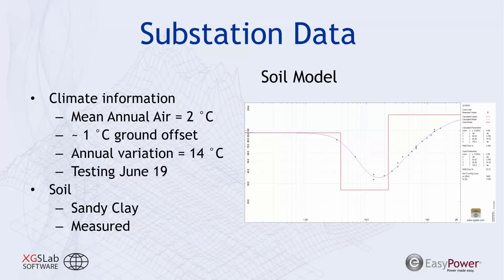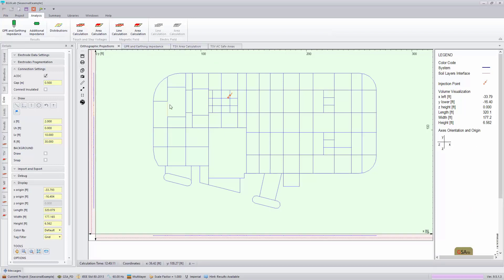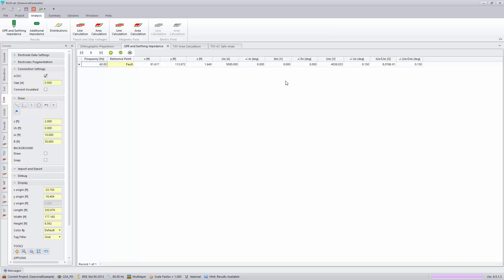Now let's look at a case study. For our example substation, the mean annual air temperature is 2 degrees Celsius — more northern regions, closer to an Alaskan region — with a 1-degree offset for ground temperature representing solar energy imparted on the earth, and an annual variation of 14 degrees Celsius. Testing was performed in summer, June 19th, and the soil is characterized as sandy clay. In the XGS Lab software, the modeled substation shows approximately 0.8 ohm impedance in summer, with a 5,000-amp fault current producing approximately 4,000 volts ground potential rise.